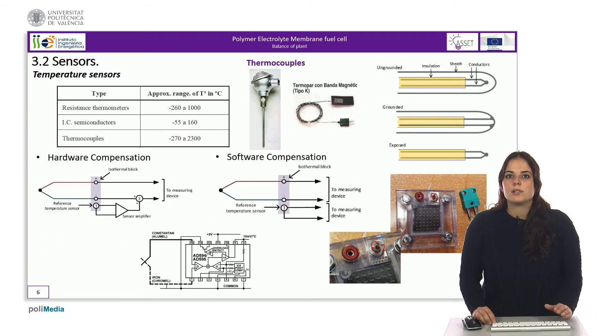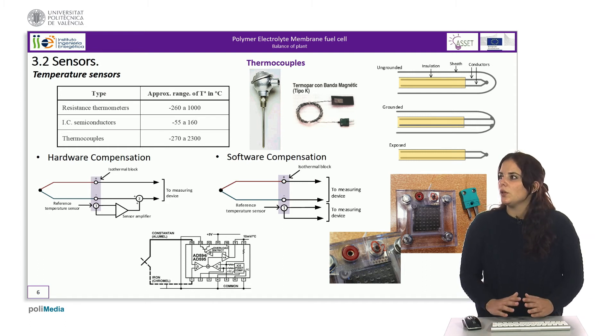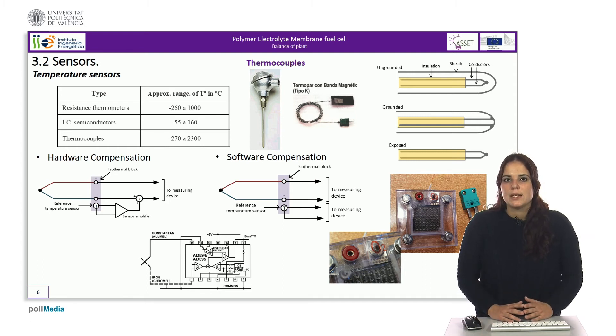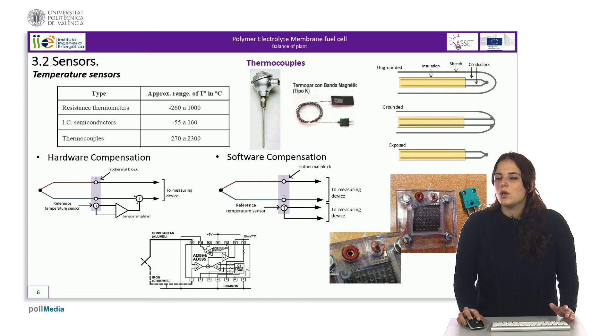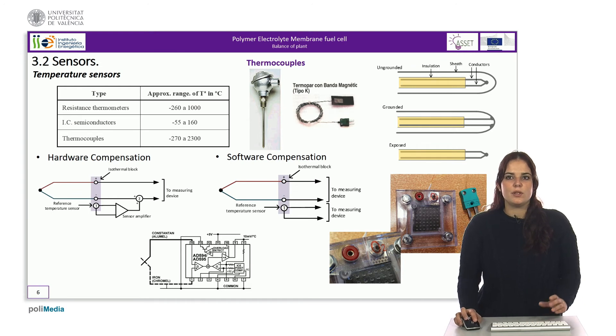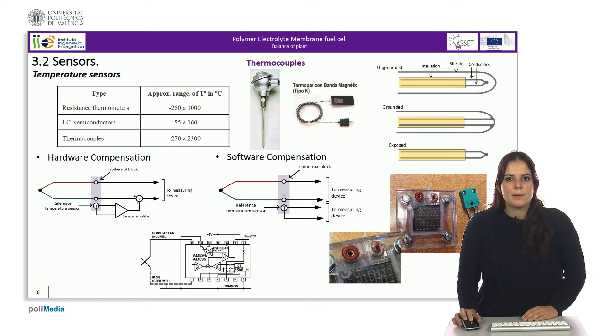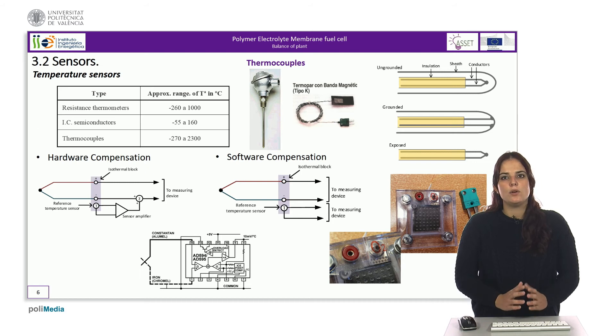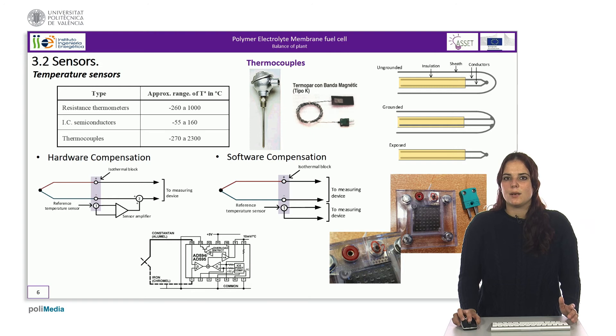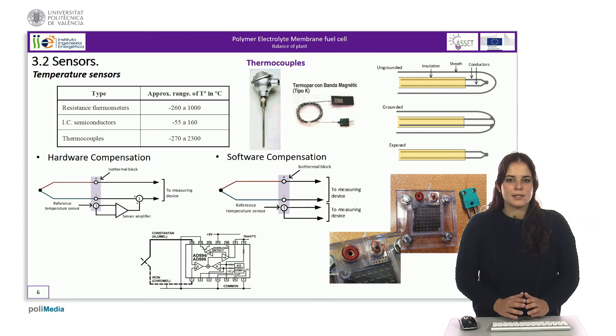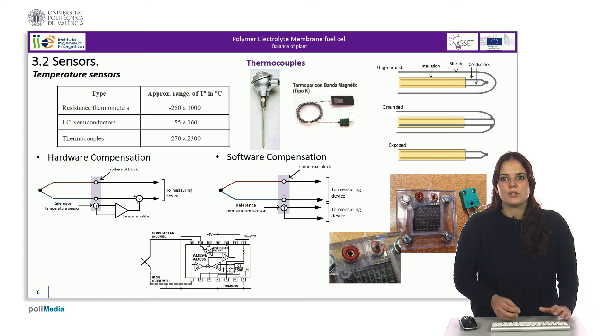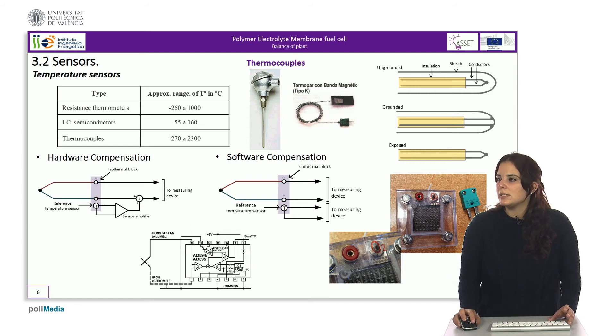Finally, thermocouples are two conductors of different metals joined at one end. The Seebeck effect describes a variation in voltage between the two conductors when the temperature of the joint varies with respect to the other end. The thermocouple may be encapsulated and attached to the metal capsule that encapsulates it, or it may be exposed. In this case, the size can be so small that it can be introduced into the stack itself to measure the internal temperature, as we can see in the pictures.